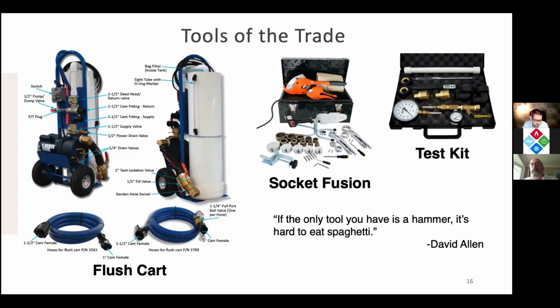For example, these flush carts will only flush a certain amount of piping, so we have to make sure the flush cart has enough power to force air out of the system. That means when designing the ground heat exchanger, it needs to use what we call a step-down header, to ensure the velocity of fluid flow when using this flush cart is high enough that those micro bubbles are forced out.